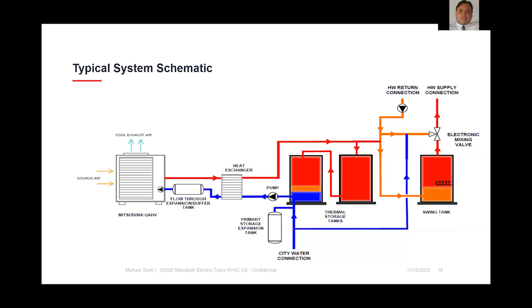most manufacturers, including Mitsubishi, are only endorsing series tank arrangements, which is what you see here. It could be a single tank system, but typically it's more than one tank. You're feeding hot water in first to what's called a hot tank upstream, and then out of the bottom of the hot tank and into your final cold tank, and then introducing cold water in that location, and pulling from the bottom side of the cold tank, obviously to maximize efficiency and heat output of the heat pump water heater.